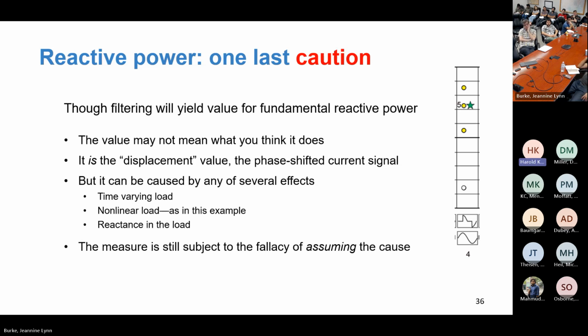It is indeed the displacement value. We often call this displacement power factor or displacement reactive power, but it can be caused by any of these effects: time varying, nonlinear, reactance in the load, hysteresis, anything like that. So it's still subject to the old fallacy of assuming the cause.